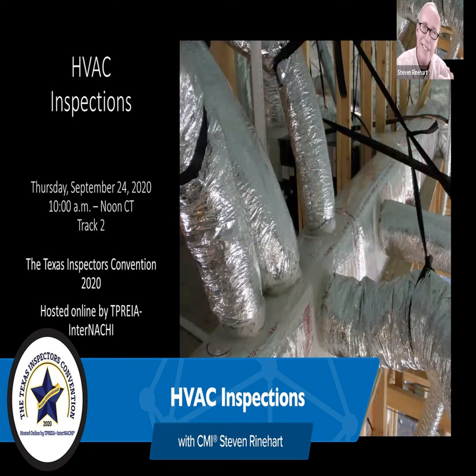Yeah, I don't know that I have seen a specific number, and there probably is something. InterNACHI has a real good class on HVAC systems. I typically see around 30 to 40 degrees of rise on heating. It might be 75 or so in the house.